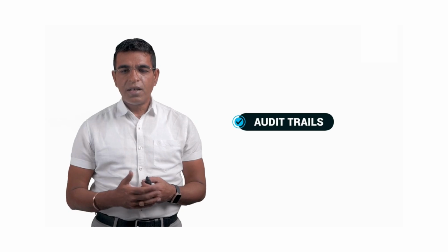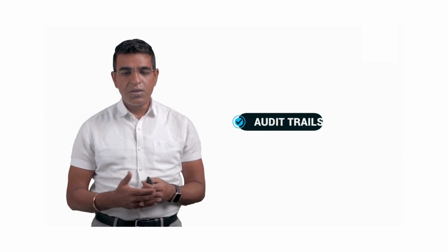Coming to another data integrity issue, which is basically the audit trails. Many times it has been seen by the regulators that laboratories turn off the audit trail functionality within the system. It is therefore not clear who has modified a file and for what purpose. It is very clear from the regulators that systems which are enabled with an audit trail, like an HPLC system or a GC system or any other system which has computer access control, the audit trail should always be kept on. It should not be kept off. Whatever is happening should be very clearly identifiable by the administrator or the regulators.